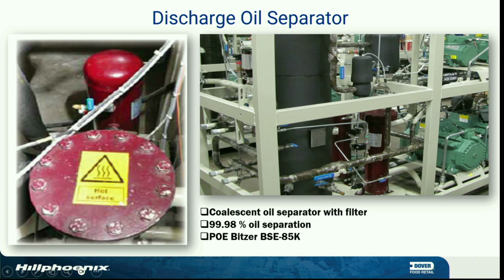We use Bitzer BSE 85K only in our racks. The simple reason is that's what's been certified by Bitzer, and also the HP sensors we use for level sensing in our oil reservoir and separator are calibrated to the same oil. All right? So if you go adding different oils in there with different additives, these conduct to the sensors and you change the capacity of the oil, and the switch is going to operate differently, right? Good.